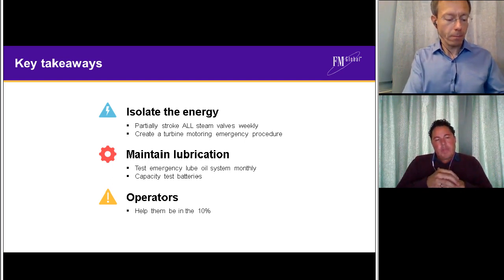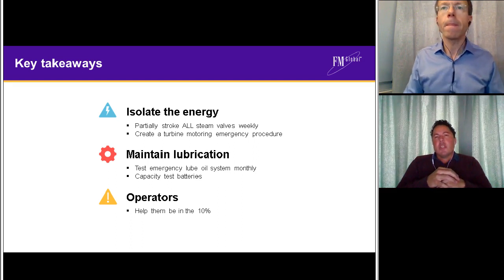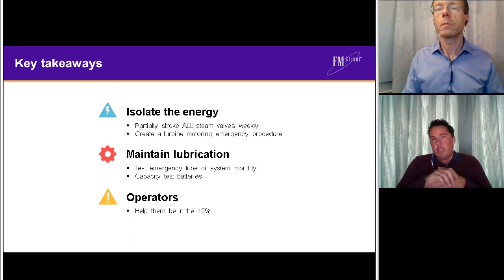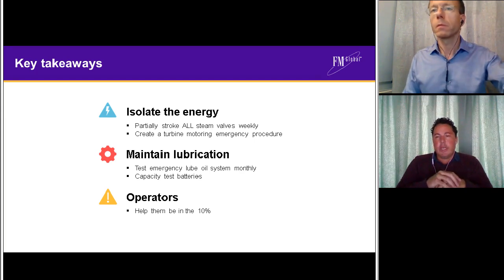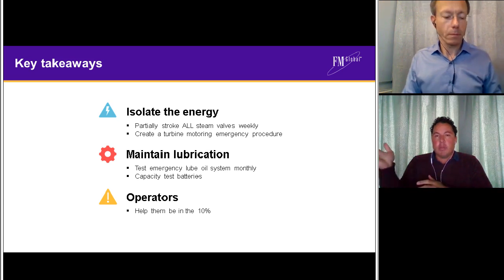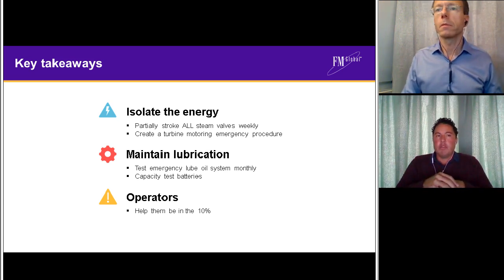I think the evolution of steam turbine safety devices over the last 5, 10, 15, 20 years is generally a good news story. I think we've spoken about it at some length today already. One of the positives is the transition away from mechanical overspeed devices to electronic overspeed devices. And I think we've touched on a few of the reasons why those are preferable. I think, by and large, the arrangement of emergency lube oil systems has improved. So most new turbines that I see today, the emergency lube oil system is piped directly onto the bearings rather than via points of failure like the coolers and the filters.